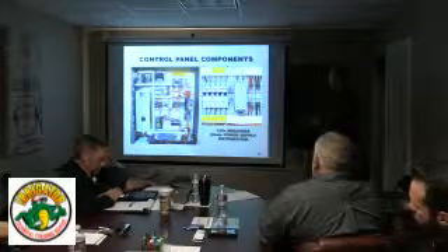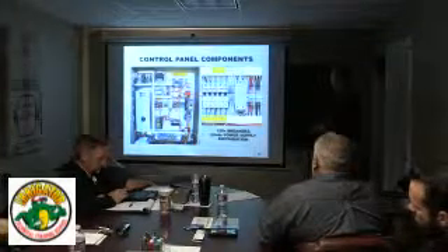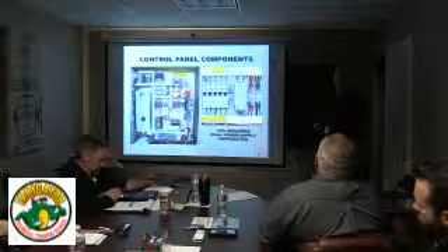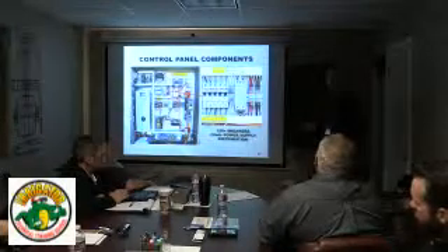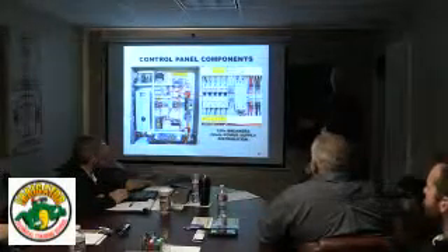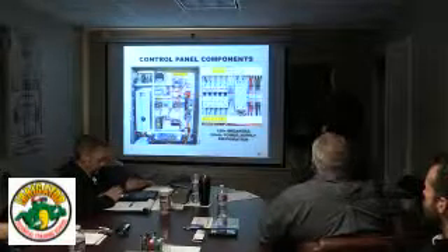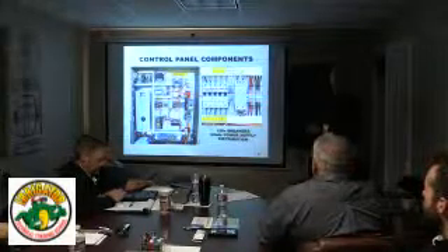So if you do pull this wire out and the LED comes back on, then you've got to start tracing where it goes to. And that's another place where that field terminal strip would come in handy. You can just pull one out at a time until you identify what it is that's shorting it out.